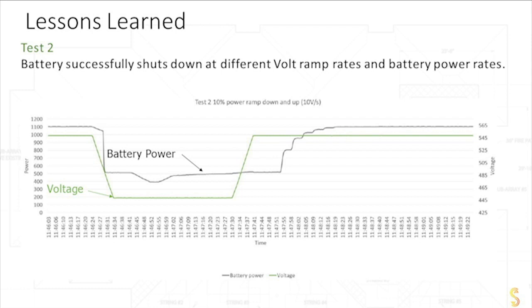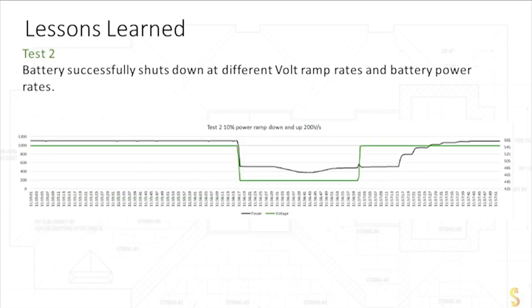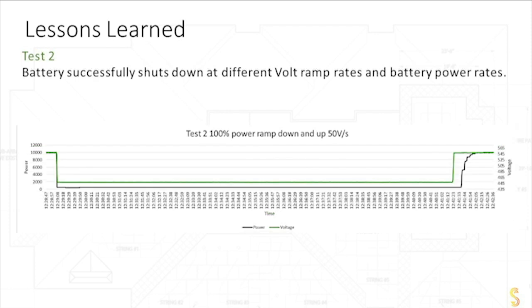And then you see when the voltage set point, set by the inverter, jumps back up, the battery sits at its lower voltage for a period of time and then turns back on after a certain amount of clearing time has gone by and it knows it's safe to export power again or to start powering up. And that's why it jumps right back up toward the right side of the graph. And we can repeat this for different speeds of voltage ramp rates. You can ramp the voltage down slow, you can ramp it up fast, and do anything in between. And so you just see different volt ramp rates, and we want to check whether the volt set point comes down quick or slow, the battery responds to it. And that's what test 2 does.